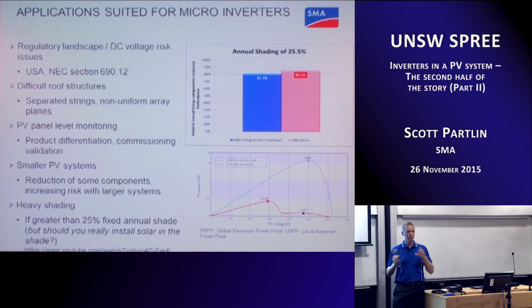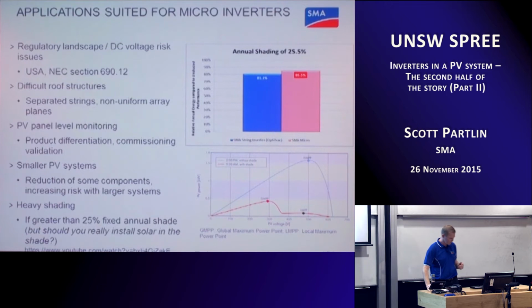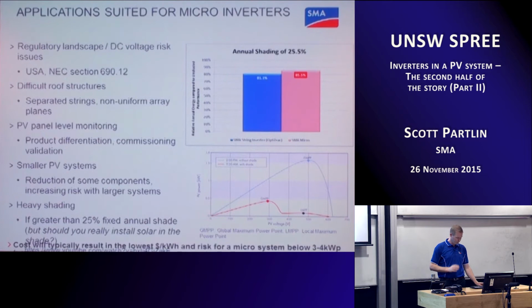One might be 1% higher, one might be 1% lower, but things like global maximum power point tracking, as opposed to just simple maximum power point tracking, which was an industry standard, say 8 or 9 years ago, are one of those things which make the analysis of how much shading before I need to go to a microinverter. That's what pushes it towards that point of about 25%. And then there are also design considerations about whether you would actually install a PV array with 25% fixed shade throughout the year. But different roofs, people want it, and if they want it and it's got those problems, then a microinverter can be the best solution for that application.